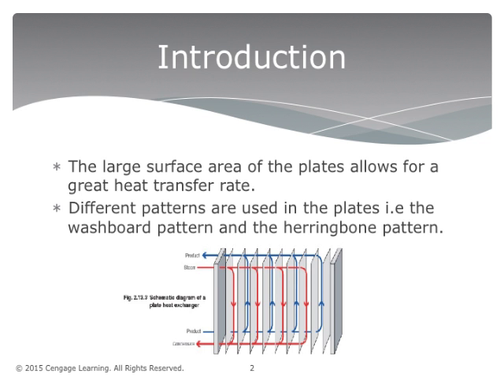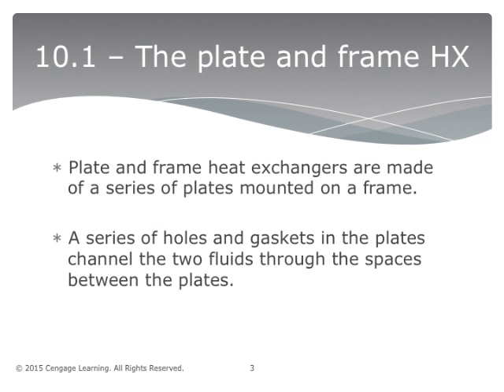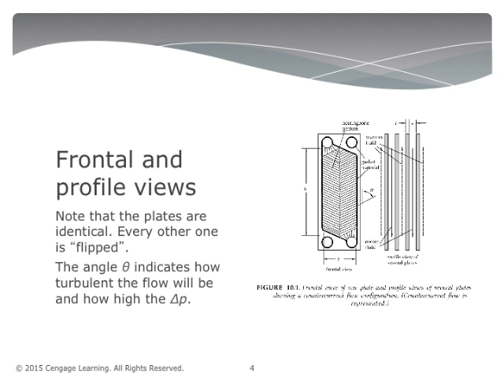Performance of the heat exchanger is a function of the chevron angle. High theta plates are able to provide higher heat transfer rates with high pressure losses, and the opposite is true for low theta plates. Plate and frame heat exchangers are constructed from metal plate frames and gaskets that separate the fluids. These heat exchangers can be used for either countercurrent or parallel flow designs. The surface of the plate in the heat exchanger is very important to the transfer of heat because it is the area in which heat is conducted.